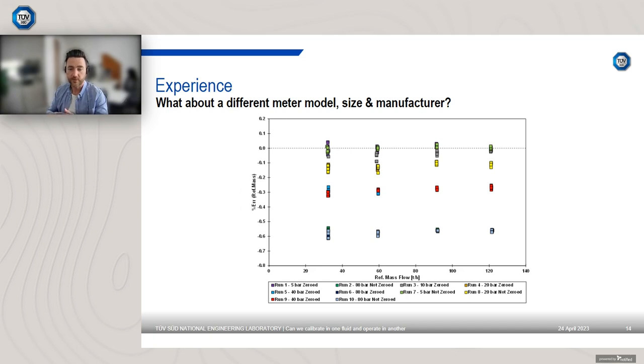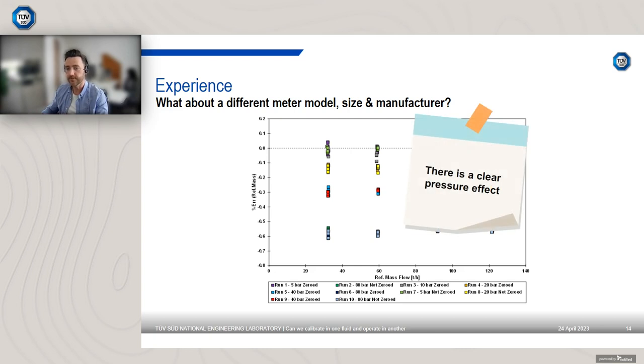So these are the meters being operated without a pressure compensation factor. What we recommend at NEL is you derive your pressure compensation factor via a traceable calibration at a traceable laboratory. So that's what we conduct. So as I say, there's a clear pressure effect that you can see there. So when people say, is there a pressure effect with Coriolis meters? Yes. Ultimately, it depends what the magnitude of that pressure effect is and whether it's significant. Is it greater than the 0.1% specification? For very small meters, it might almost be not noticeable because the uncertainty of the device and the size of the pressure effect are all merged into one. But for larger meters, we're seeing a larger pressure effect.